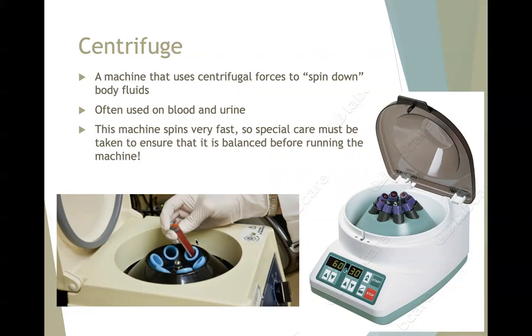So if you don't have 2 tubes, let's say you only have 1 tube of blood, you will grab another tube and fill it with water up to about the same amount of blood that's in the other tube. And it needs to go directly across from that tube to balance out the centrifuge. If you only put 1 tube in the centrifuge, it's going to be extremely unbalanced. The centrifuge will actually rock back and forth. And I have seen them fly right off the table. So we have to make sure that we're balancing them, even if we only have 1 blood sample.